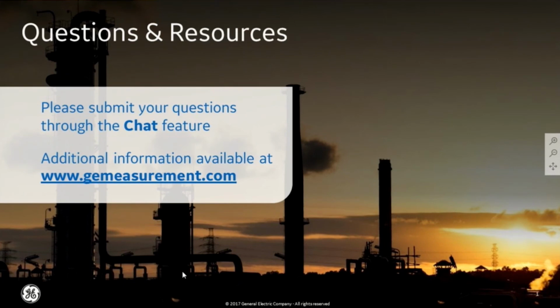Yep, sure can. That's just a function of having a standard of the materials, and it'll calibrate to it. As I demonstrated, I used the IIW block because that's a very ubiquitous block. There are lots of those around the industry. If you have a particular calibration standard that's not the kind of thing you run into every day, you can build your app around that.